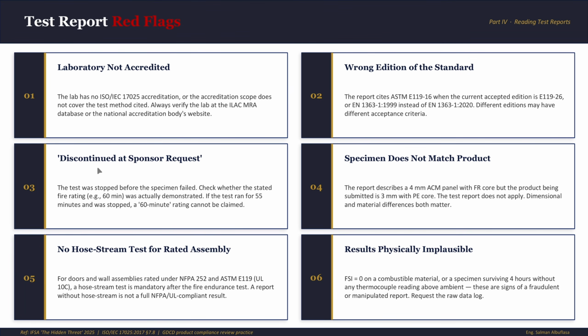And then, discontinued at sponsor request. That's suspicious. The test was stopped before the specimen failed. So let's say I ran a test for 55 minutes and stopped it before my product failed. I cannot claim the product is 60 minutes fire rated. The demonstrated rating is 55 minutes. That's it. Not 60, not 50, exactly 55 minutes. Always double check and verify when you see discontinued at sponsor request. There's always something wrong you can find there.